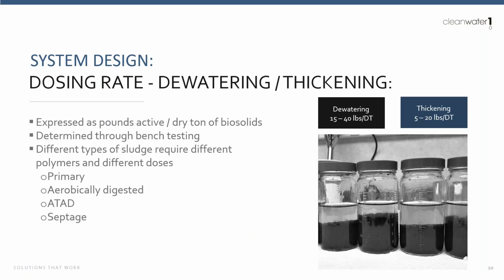And then thickening, you're around 5 to 20 pounds per dry ton. So this can always help as far as the initial design of these systems, but it's always important to really get that bench testing done so that we know specifically what type and what dosage of polymer we need to be using.